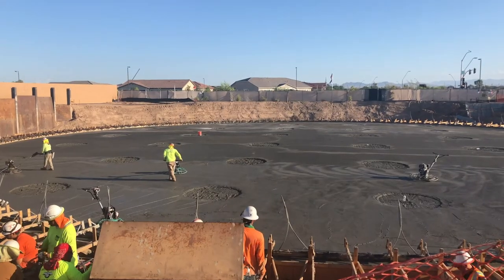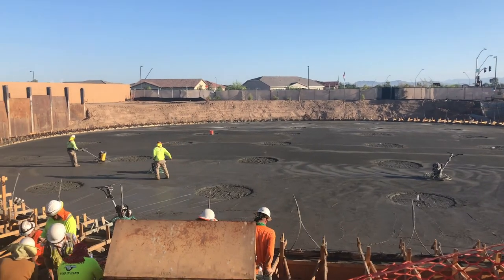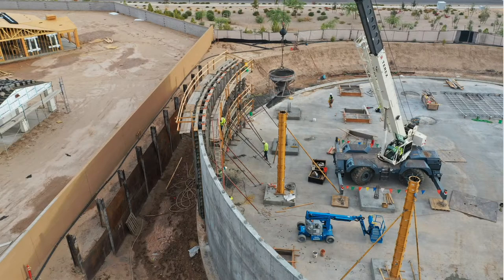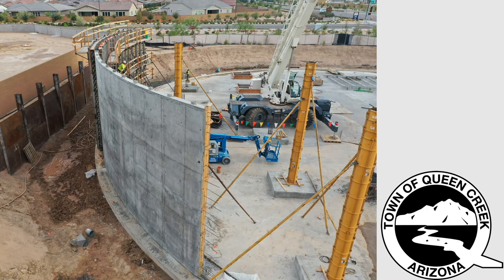The concrete was completed in three phases. The first phase — the floor — was completed in one continuous pour and includes 540 yards of concrete. The second phase was for the walls and columns, which includes 460 yards of concrete, completed over 22 consecutive days. The walls include 121 internal pre-stressing tendons made of high-strength steel with over 137,000 pounds of force on each tendon.